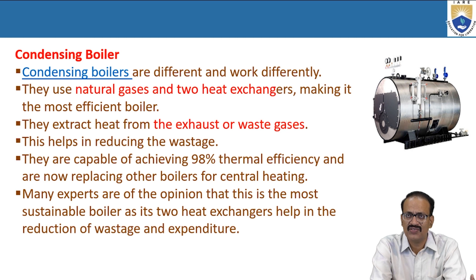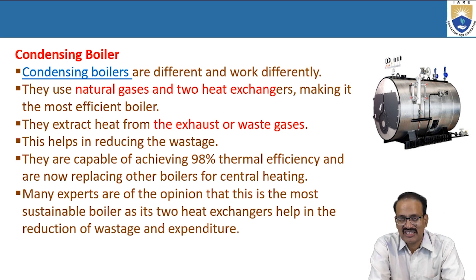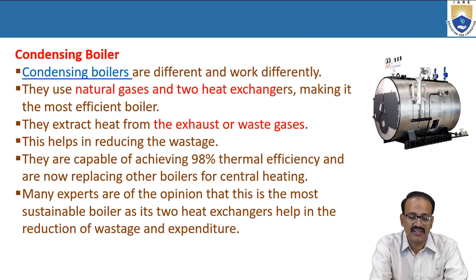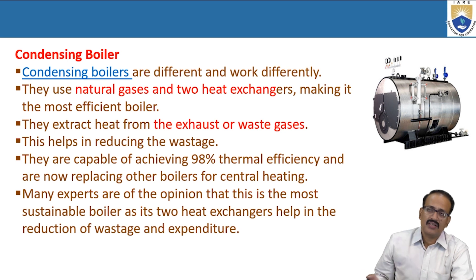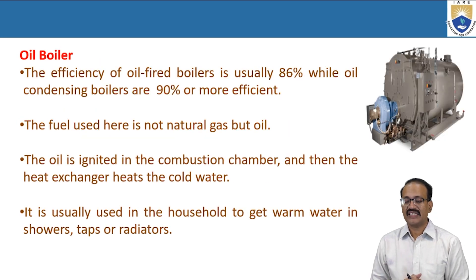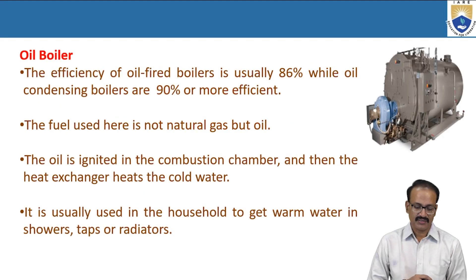The condensing boiler uses two heat exchangers and natural gas, and is able to absorb heat from the flue gases also. That is why the efficiency of this condensing boiler is up to 98%. There is no doubt that this is the most sustainable boiler. The oil boiler comes next with 86% efficiency, using oil rather than natural gas.